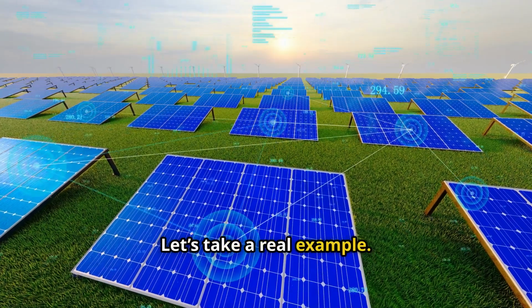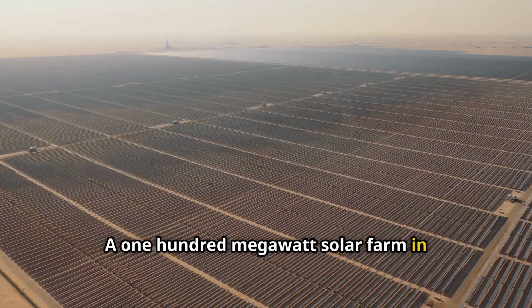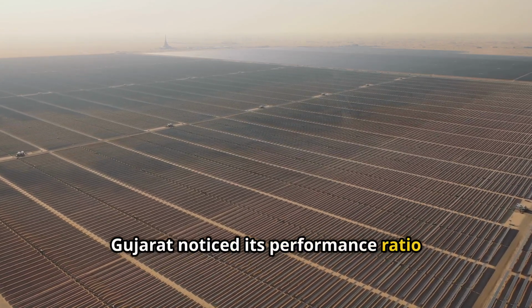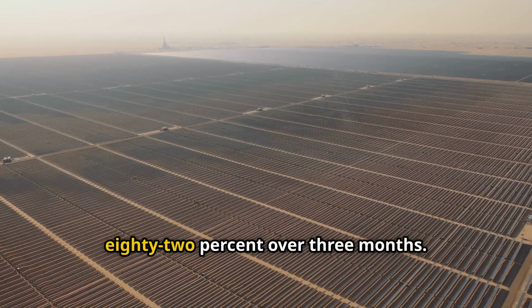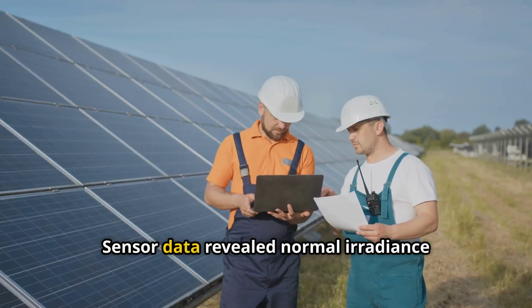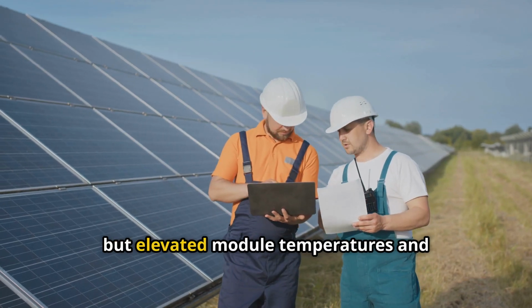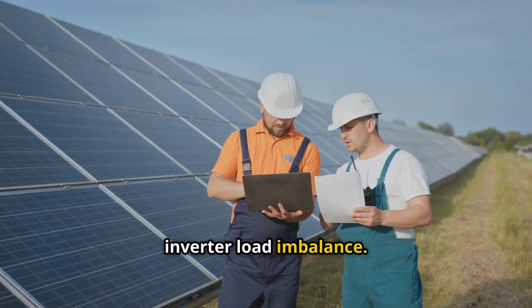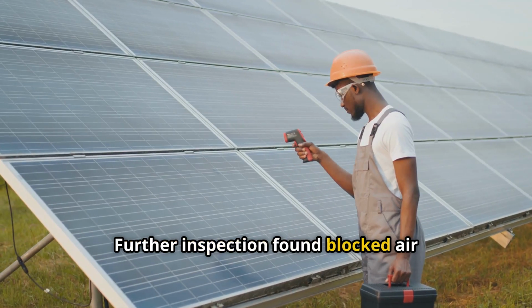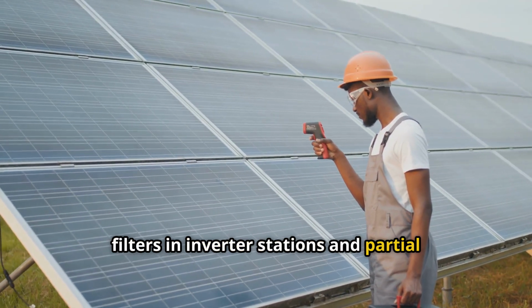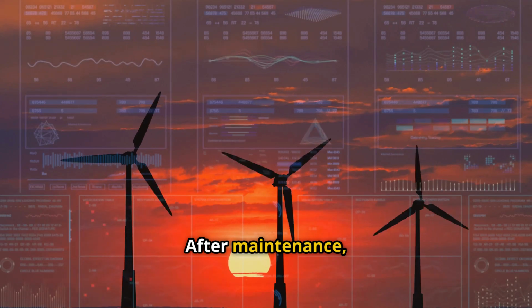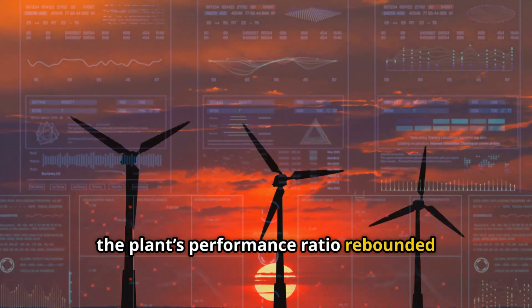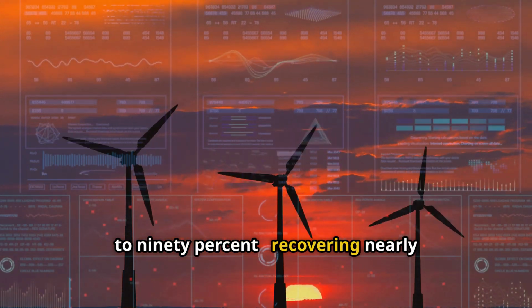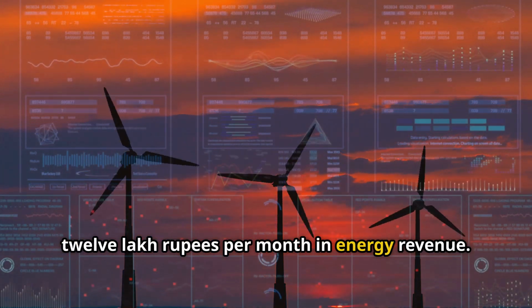Let's take a real example. A 100-megawatt solar farm in Gujarat noticed its performance ratio dropping from 88% to 82% over 3 months. Sensor data revealed normal irradiance but elevated module temperatures and inverter load imbalance. Further inspection found blocked air filters in inverter stations and partial tracker misalignment. After maintenance, the plant's performance ratio rebounded to 90%, recovering nearly 12 lakh rupees per month in energy revenue.